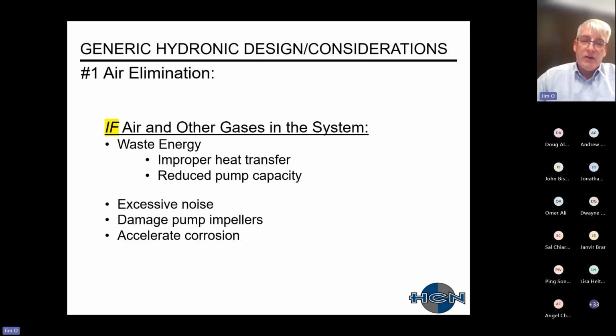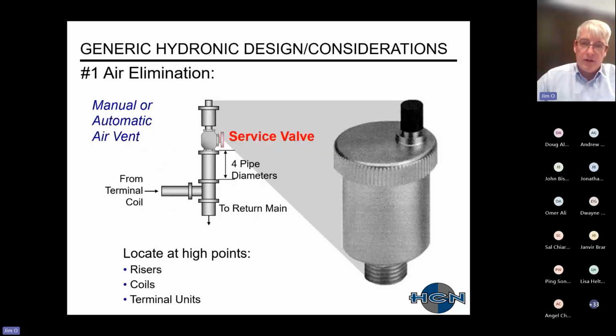It could damage your pump impellers, which are sort of a pain in the butt to replace. And another thing too is that air and gas in the system do accelerate the corrosion on the interiors of your pipes. So how can you get rid of air in your system? How to eliminate it? What I don't think is done enough is to have small, manual or automatic air vents periodically through your system.